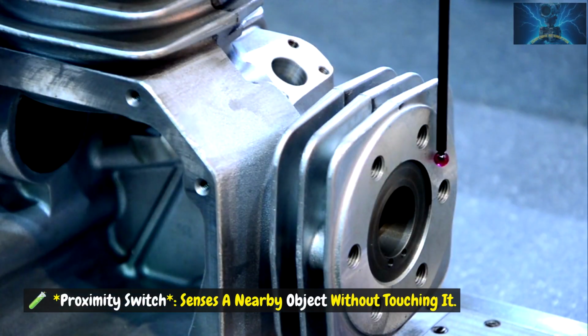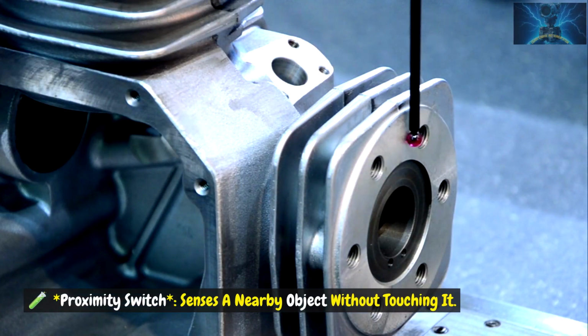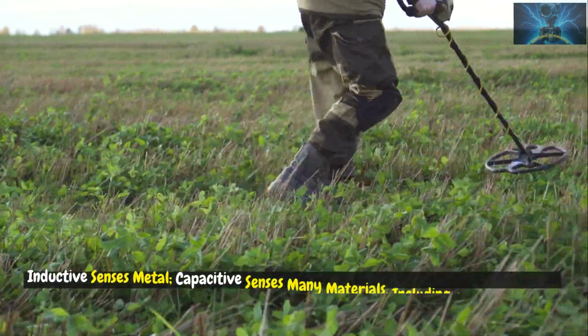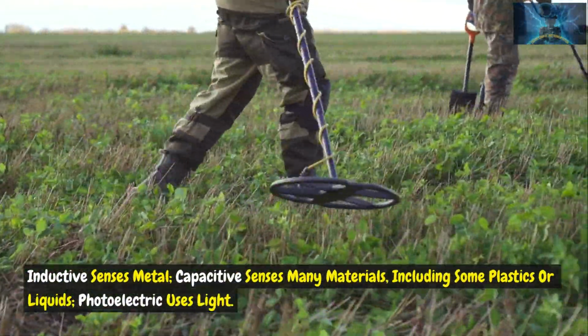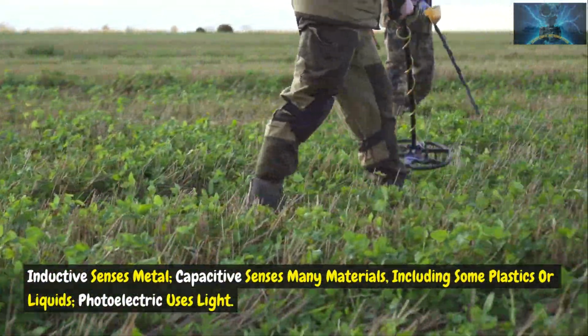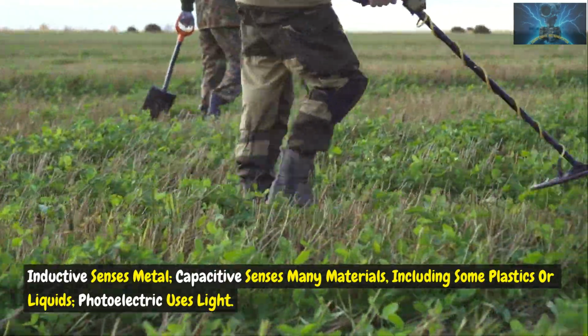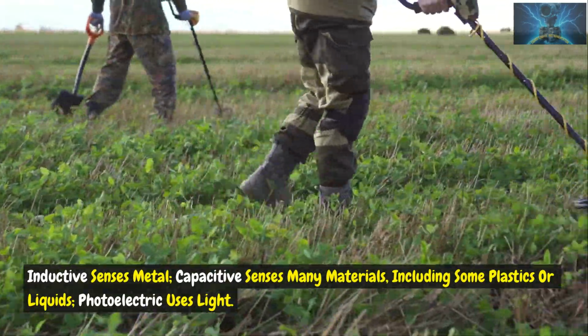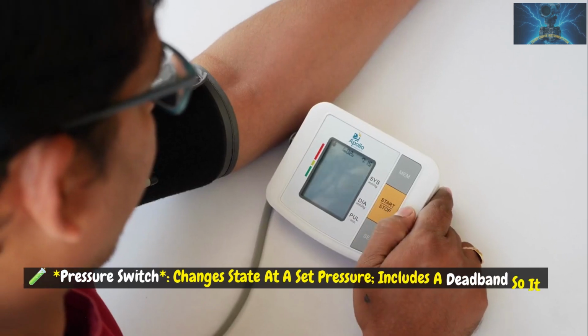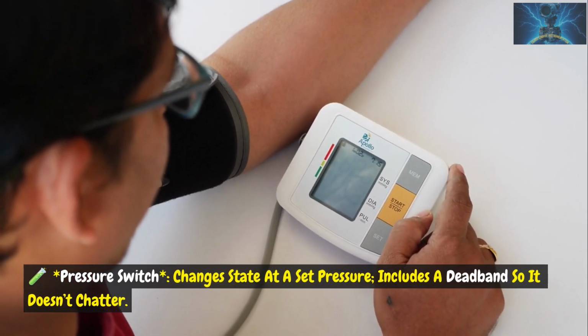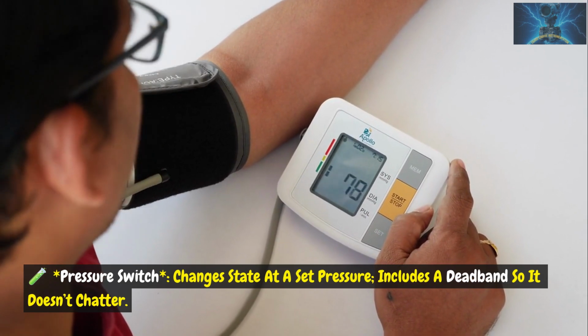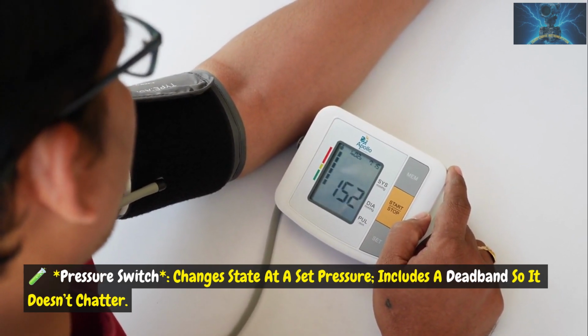Proximity switch: senses a nearby object without touching it. Inductive senses metal. Capacitive senses many materials, including some plastics or liquids. Photoelectric uses light. Pressure switch: changes state at a set pressure. Includes a dead band so it doesn't chatter.